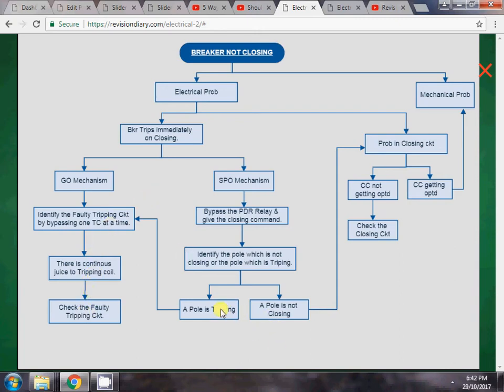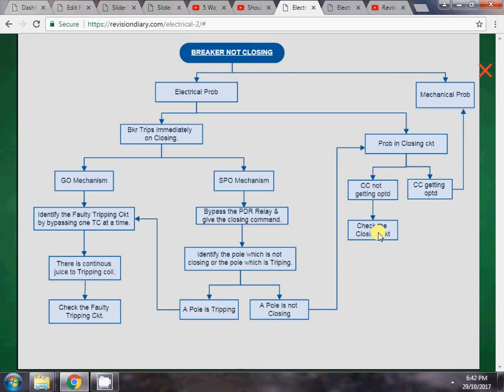If a phase is not closing, the problem can be in the closing circuit. There are two scenarios: the closing coil is getting operated, or the closing coil is not getting operated. If the closing coil is not getting operated, we check the closing circuit for an open circuit. There can be many problems such as an open closing resistance or faulty auxiliary contacts of the breaker.